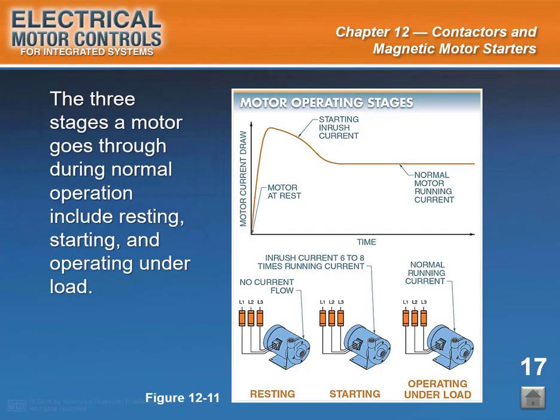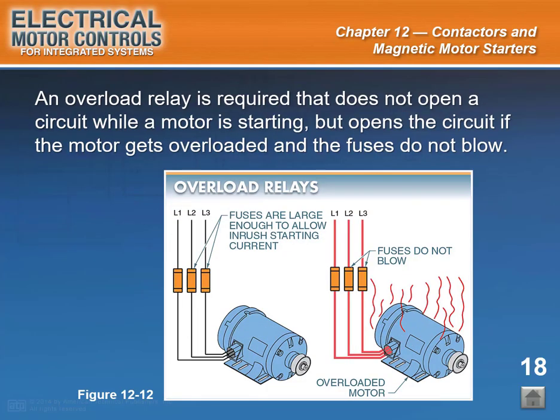Slide caption: the three stages a motor goes through during normal operation include resting, starting, and operating under load. See figure 12-11. A motor at rest requires no current because the circuit is open. A motor that is starting draws a tremendous inrush current that is normally 6 to 8 times the running current when the circuit is closed. Fuses or circuit breakers must have a sufficiently high ampere rating to prevent the immediate opening of the circuit caused by the large inrush current required for a motor when starting. End of slide 17. Start of slide 18.